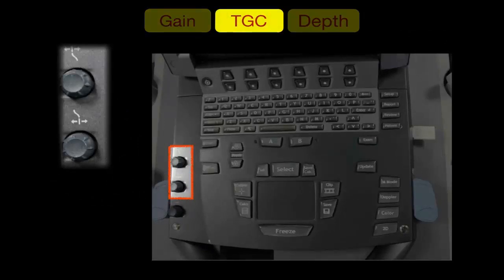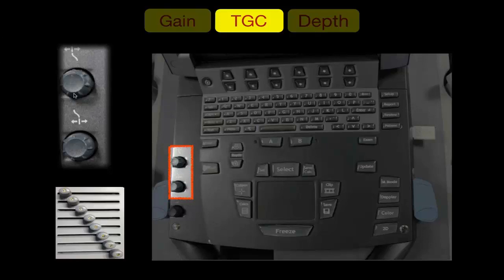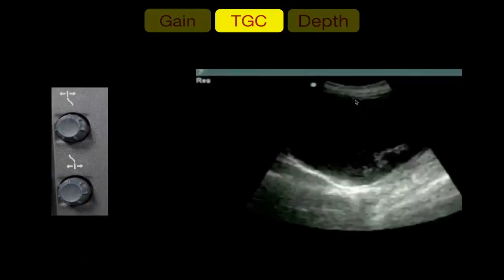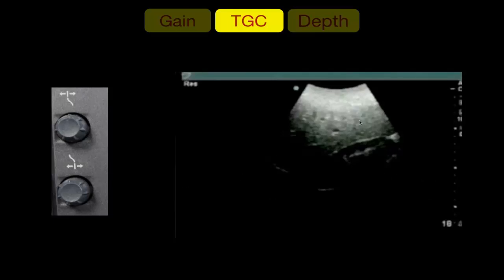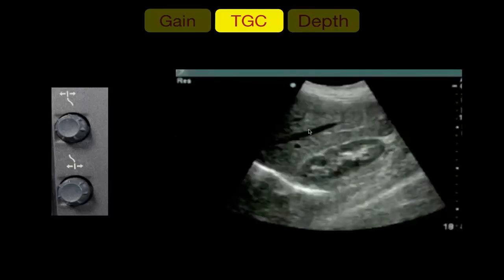TGC allows you to adjust brightness with better control of the near field or far field independently. One button adjusts the near field brightness while another adjusts the far field. For example, if the near field is very dark and the far field is very bright, you increase gain in the near field and decrease it in the far field. You want the image balanced so blood in the hepatic vein appears anechoic, the diaphragm appears hyperechoic, and structures like the liver or kidney cortex appear in between.